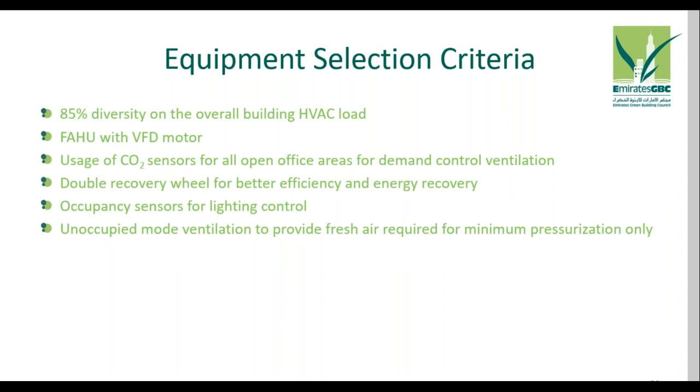That's what ASHRAE 62.1 notifies. We cannot compromise the parameter of space, but the typical office buildings have high density and high occupancy in the daytime hours, say from 8 o'clock in the morning to say 7 o'clock in the evening. After that, the occupancy level drops down to almost zero in most of the spaces. In such times, the fresh air pertaining to occupancy can be absolutely brought to zero.